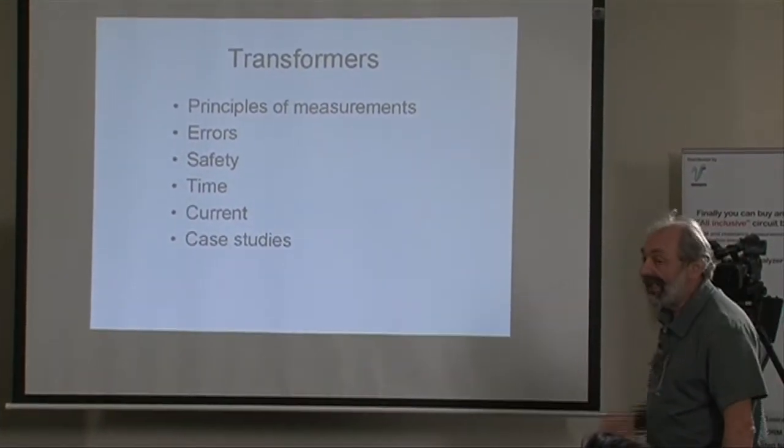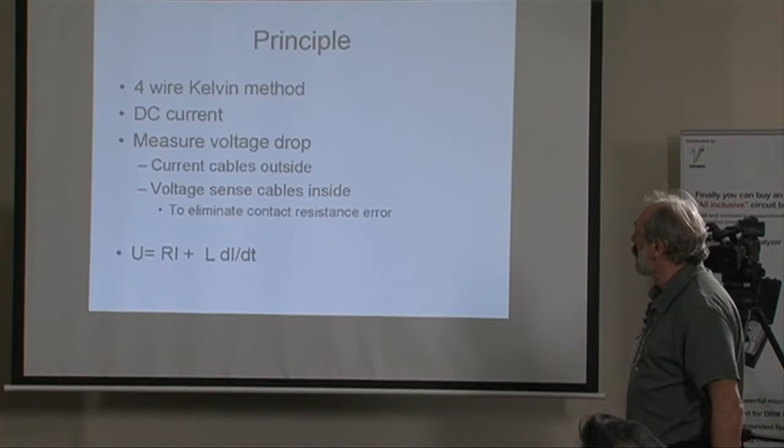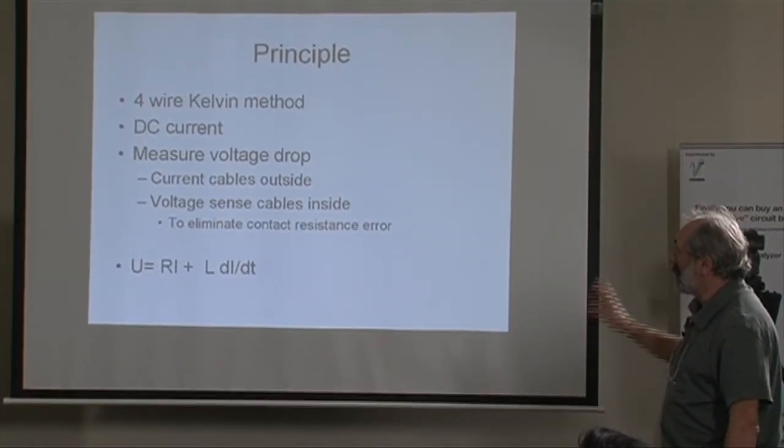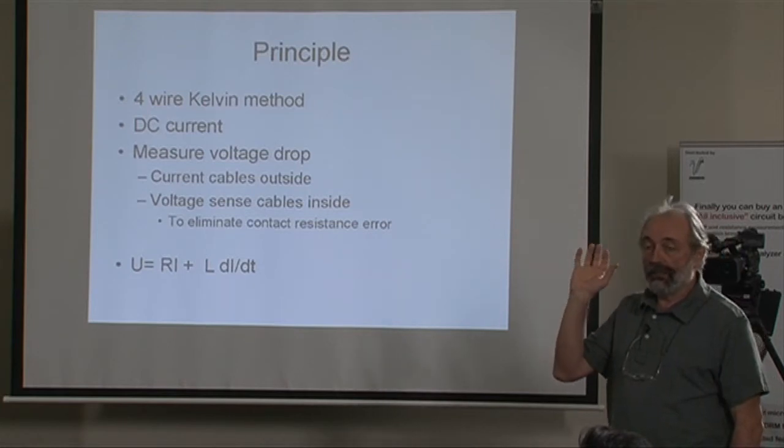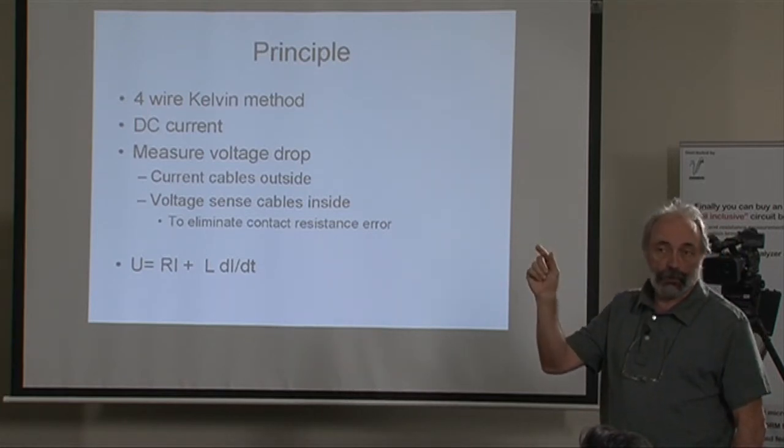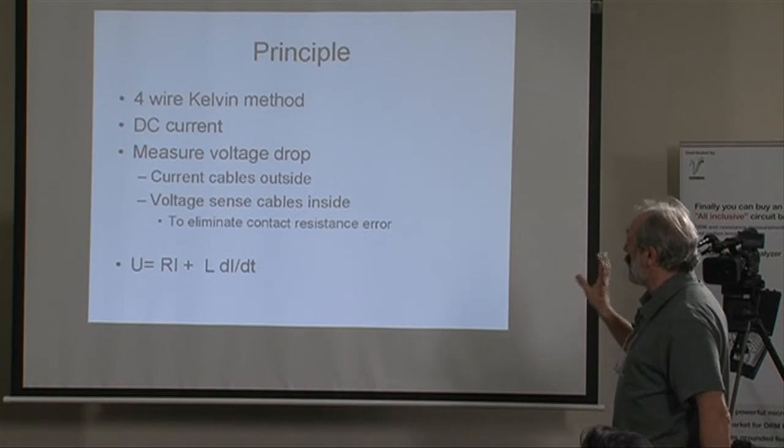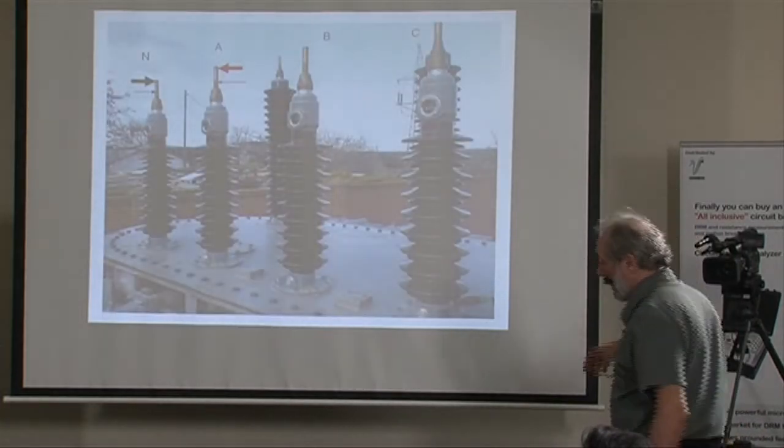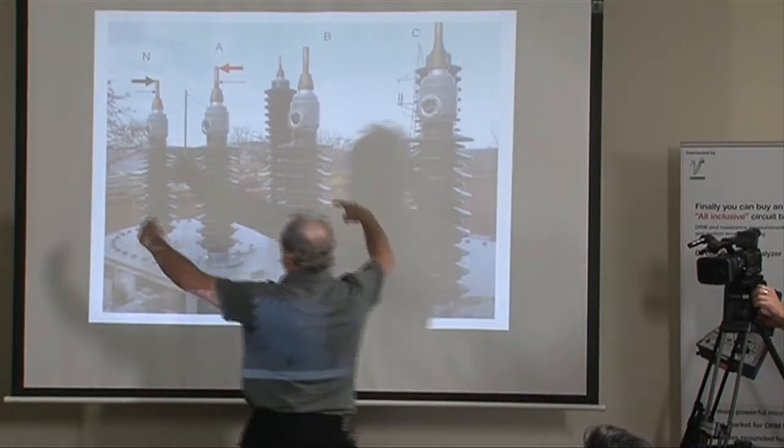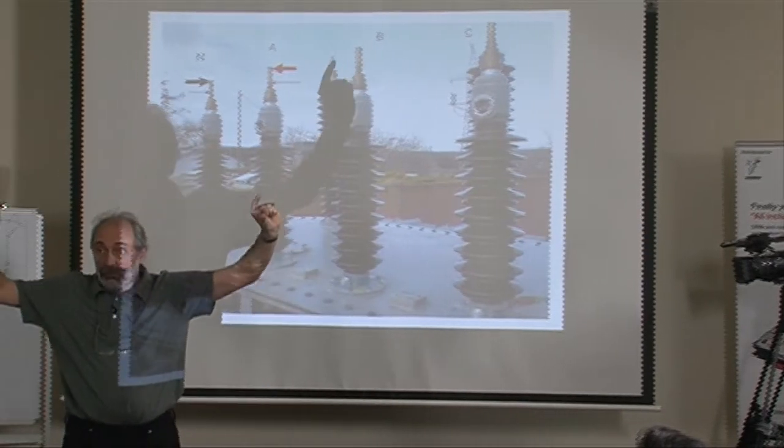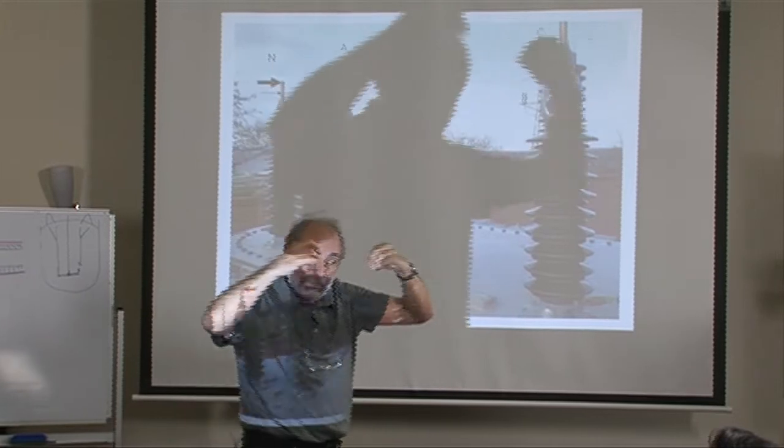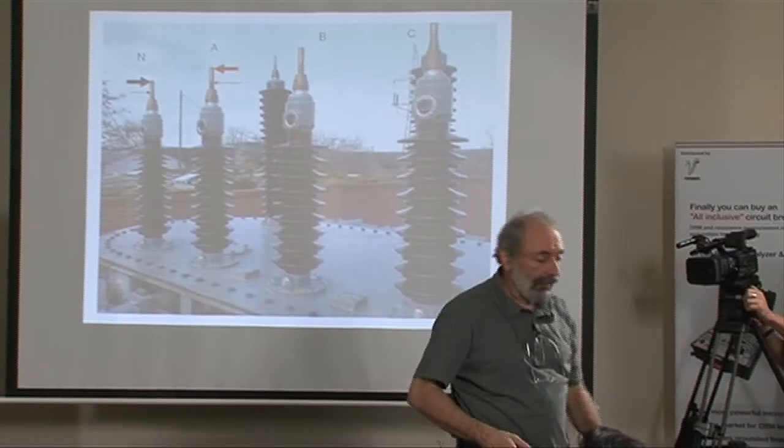First issues: you do a four wire Kelvin method, which means you apply current and you measure voltage drop. Easy. How do you connect? You put current up here, so it's a thick wire, and you put voltage inside, it's a thin wire.